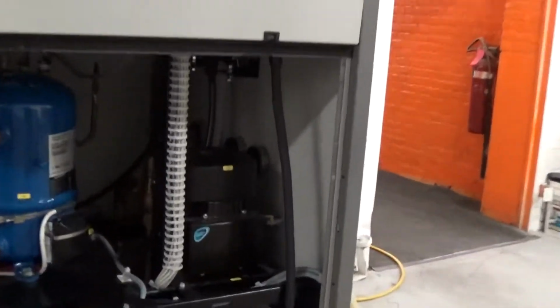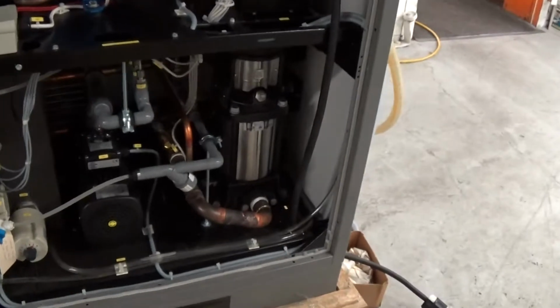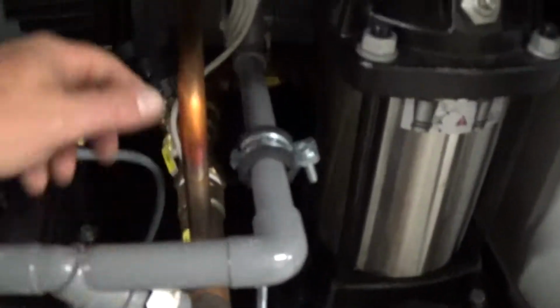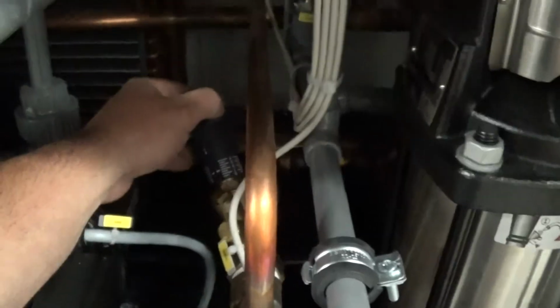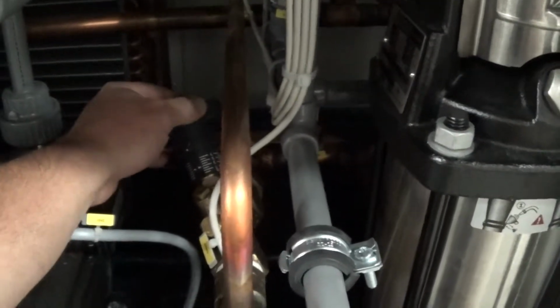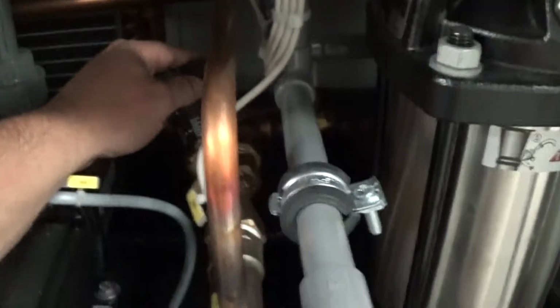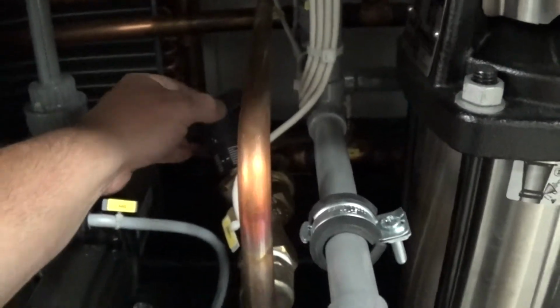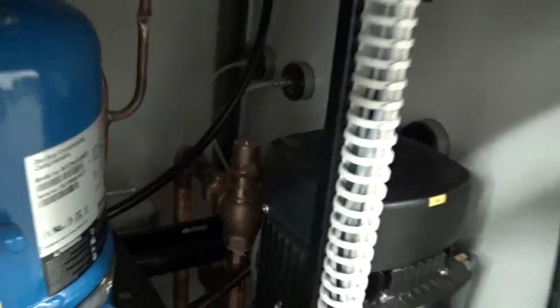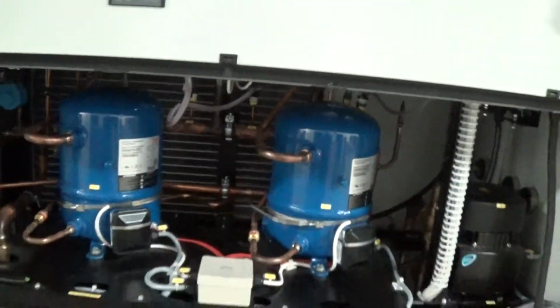This is your primary pump here, and this here is basically a flow control. We'll have it set at what we feel is a nominal position. And in addition to this flow control, to control the flow out to your process, there's also an internal bypass here, and that's adjustable. Okay, so if your process is too restrictive flow-wise for this chiller, we can adjust that internal bypass to direct a little bit more flow back to the heat exchanger in this chiller.